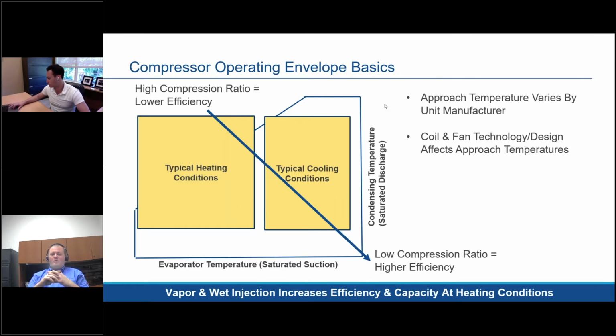And approach temperatures, coils, pumps, how much water or air you're moving through the system has a big impact on what specific temperatures you're going to need to operate at. It also has a big effect on how much hot water you can actually get out of the system. Can you make 140-degree hot water to replace most condensing boilers, or, in some extreme conditions, replace some older boilers that may go up to 150 or 160-degree hot water? A lot of that has to do with what type of coil and what type of system design you're using.